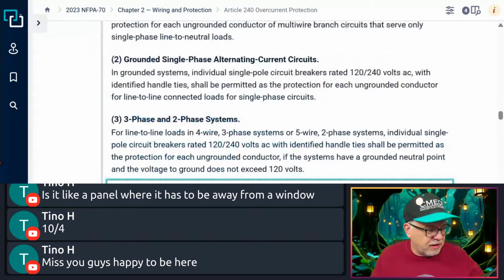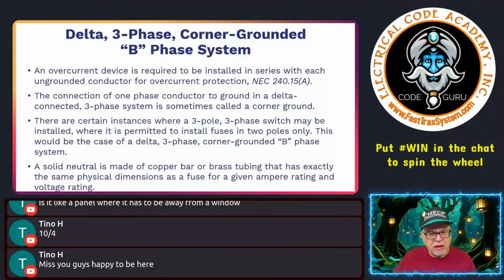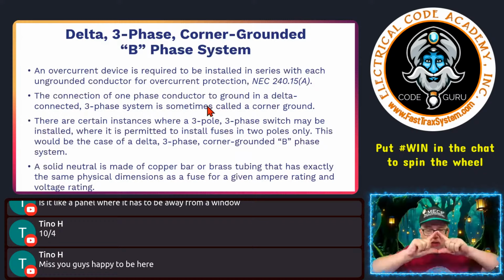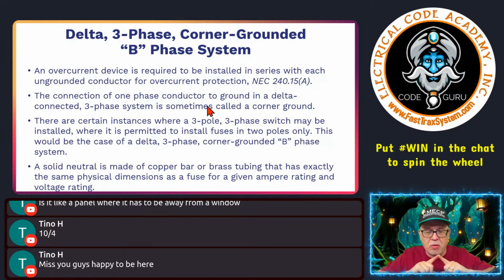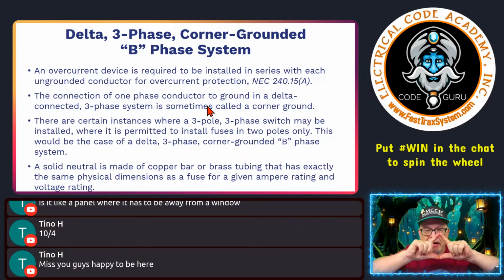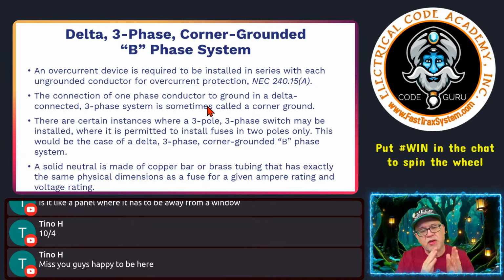So back to the lesson, in case we have anything we need to refer back to, we'll keep the code handy. It says the connection of one phase conductor to ground in a delta connection, three-phase system is sometimes called a corner grounded delta. I don't have a picture of that, but y'all know a delta is a triangle format, and each one of these is a phase or winding. So when you talk about a panel with three phase, that is phase to phase. When you talk about a single phase, which is typically a transformer that only has one winding that's center tapped, it is 240, let's say, across the full winding, but to the center it's only 120.